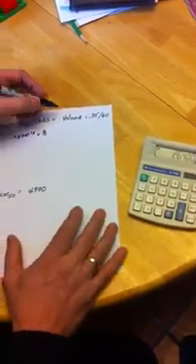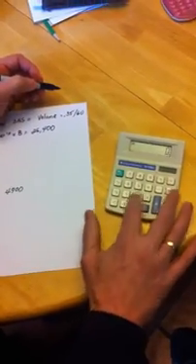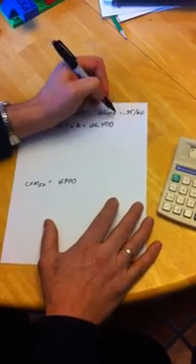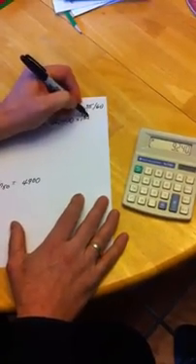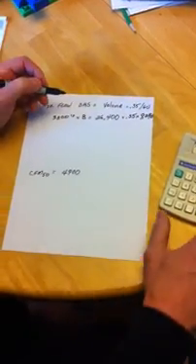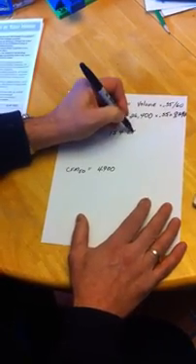So this house equals 26,400 for volume, times 0.35 is 9,240, and then we divide that by 60, which equals 154. So we need 154 CFM of ventilation in this house.